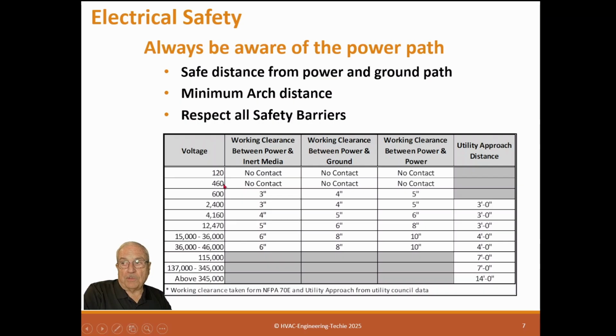At 460 volts, anything between 120 is the same. No contact. You don't have to have an inch of clearance, but just don't let it touch. At 600 volts, the clearances jump to 3 inches, 4 inches, and 5 inches. At 2,400 volts, you can see it's still the same. At 4,160, it goes up to 4 inches, 5 inches, 6 inches. So between power and ground, you have to have at least 5 inches, 6 inches at 12,470. And if you go up to 46,000 volts, you can see it's 6, 8, and 10 inches.